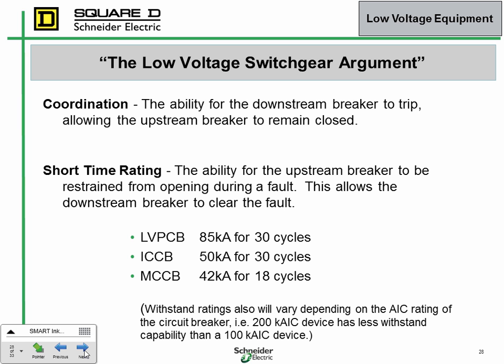There are some manufacturers where off is off, and it's just short time at that point. There's no protection to that breaker, and that's why they introduced that code requirement, to have differential relaying or something at that point. Our breakers, off doesn't necessarily mean off. It just means the override is built in to move that curve way over to the right. Okay, so we don't have to worry about that with our breakers. And that's what I was talking about, some of the code changes. Off isn't necessarily off. Gotcha. Some manufacturers it is. Then yeah, you have to shift it all the way up.